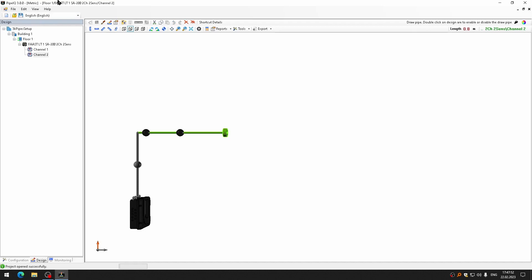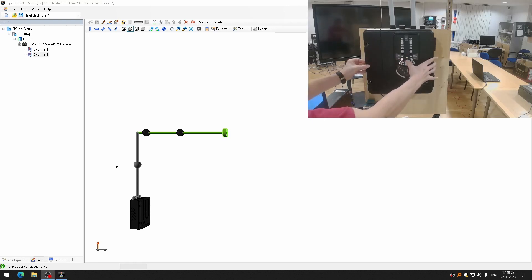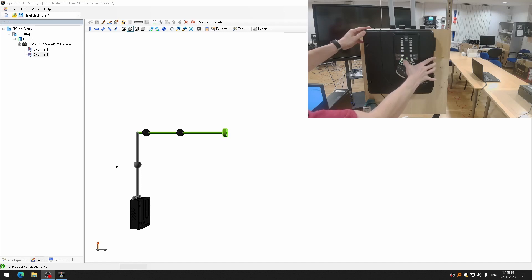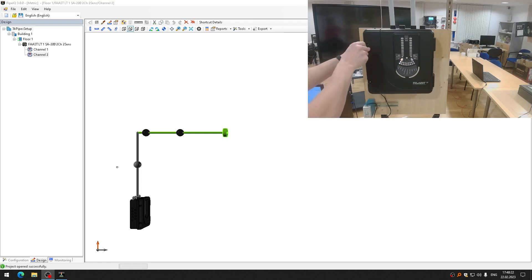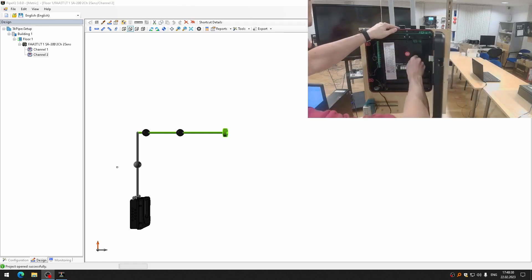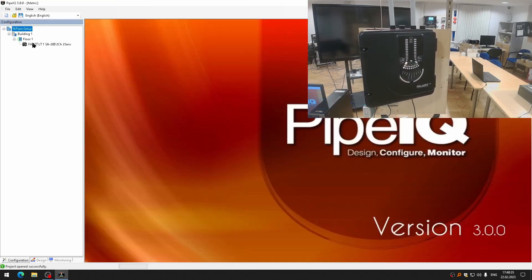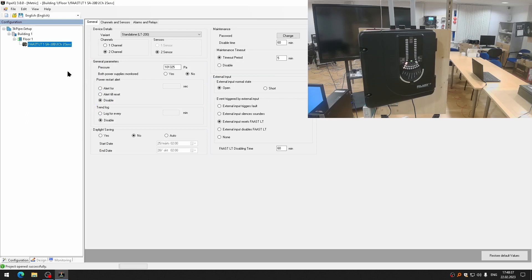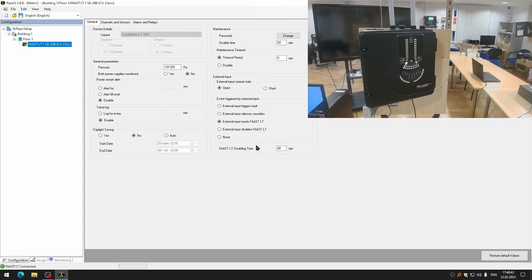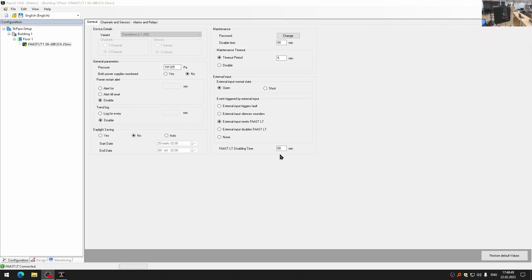I will save the project and now I will send the configuration into my detector. For that, I will enter the maintenance mode. I am now in maintenance mode and I will connect the USB cable. Connect to the device. I will use admin password 3111. Let me make it smaller. Send configurations. Send configuration successful.